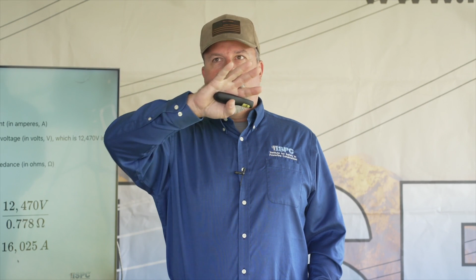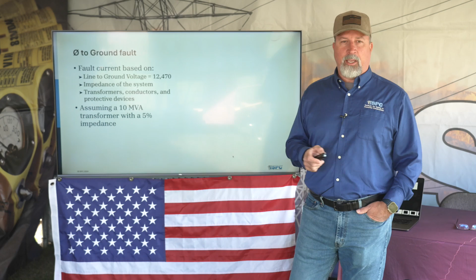So here's the same example, just going phase to ground instead of phase to phase, okay? So again, your line to line voltage, 12,470. Your line to ground voltage, 7,200. Impedance of the system, all the same. Taking that same 10 MVA transformer with a 5% impedance, okay? So you take your voltage line to ground, 7,200, divided by that same impedance, you're still over 9,000 amps in that case, okay?